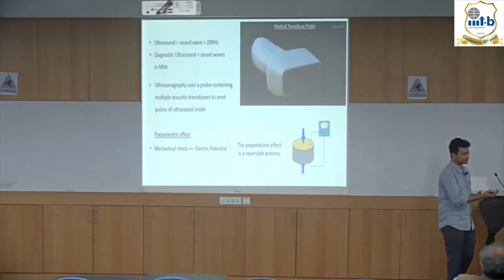So the wavelength is smaller. Yes. So the ultrasound probe contains several acoustic transducers. To send the ultrasound pulse, these acoustic transducers are made of piezoelectric crystals. So whenever a change in electric pulse is applied across these crystals, a corresponding change in mechanical stress occurs across the crystal. This effect is called the piezoelectric effect, which is exploited in production and reception of ultrasound and in their echoes.